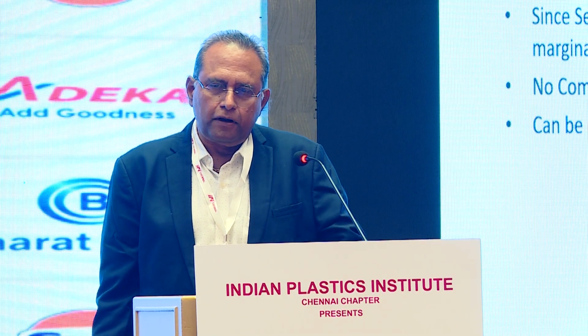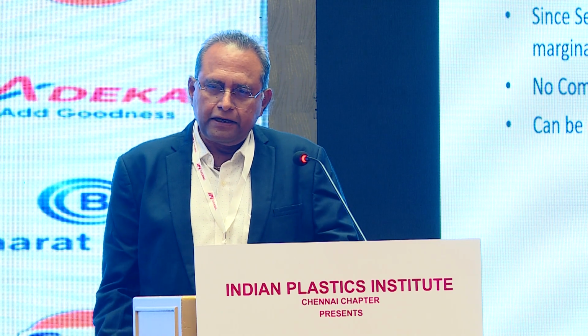Additional benefits are, since it is an inverter based system, the starting current will be very low. So you can have smaller generators for standby. So generator capacity can be low. And also, most of the hydraulic machines now come with servo cooling. So the servo cooling heat rejection will be almost 40 to 50% lower than the normal standard motor power packs. So the chiller loads can be reduced. And we can connect multiple chillers in modules, so even though it is modular, we have no restriction in the capacity of the chiller.